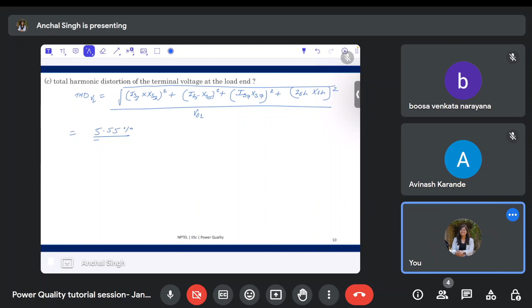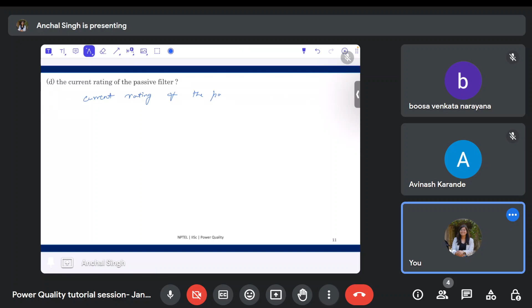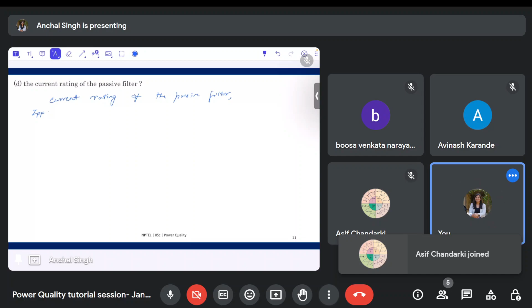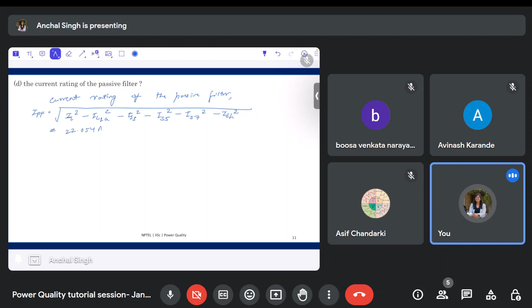Let us move on to the next part. So the next part is the current rating of the passive filter. So we know that after compensating for all these currents, whatever currents are remaining will define the current rating of my passive filter. So in order to calculate the current rating of the passive filter, let me call it IPF. It will be equal to under root of load RMS current square minus active part of the load current minus IS3 square minus IS5 square minus IS7 square minus ISH square. After compensating for all those harmonics and the active component, whatever is remaining will define the current rating of my passive filter. So this is the current rating.